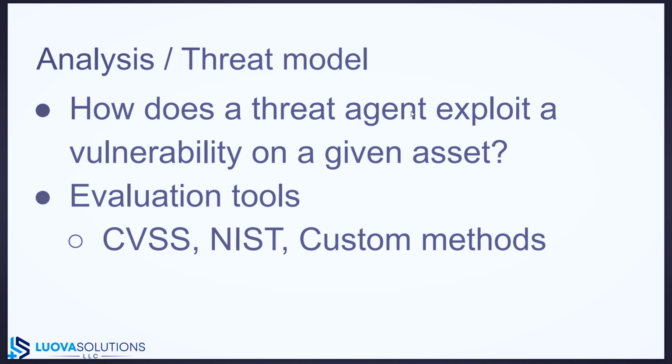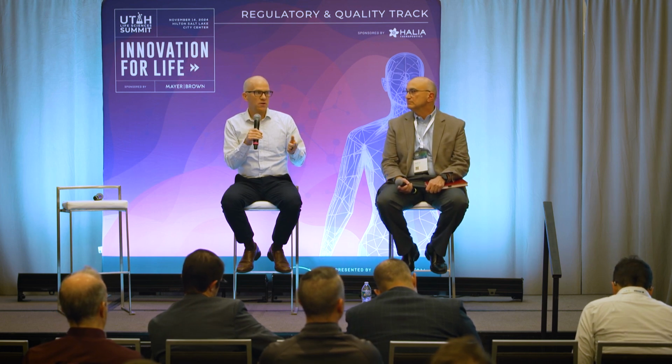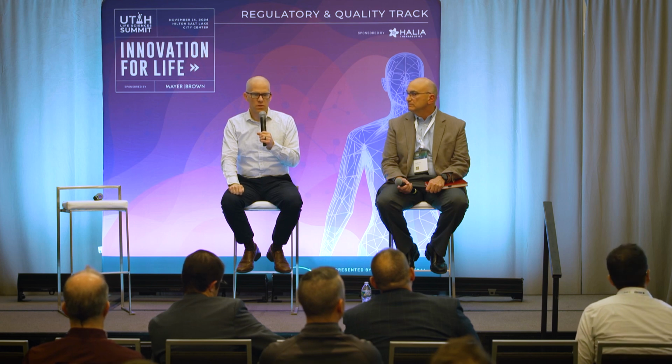So then, like all things, we have this list, we need to evaluate it for its risk. So in 14971, it talks about the probability of occurrence and the safety of your device. We can't use those for a cybersecurity risk analysis because this isn't safety focused. This is security focused. And so the FDA guidance document talks about using CVSS, which is the Common Vulnerability Scoring System. It also talks about a NIST standard that talks about exploitability and impact, which is what we're going to talk about. And you could also create a custom method for how you want to evaluate your cybersecurity risks.